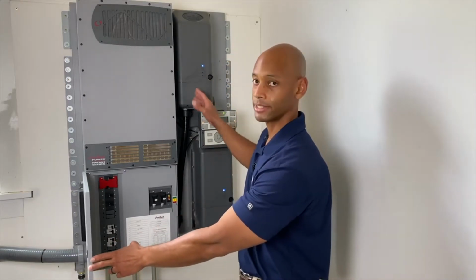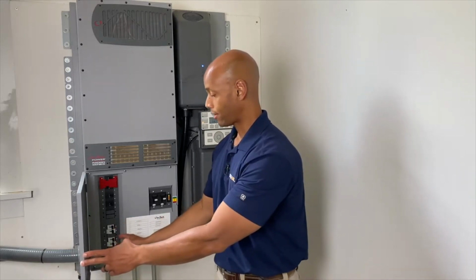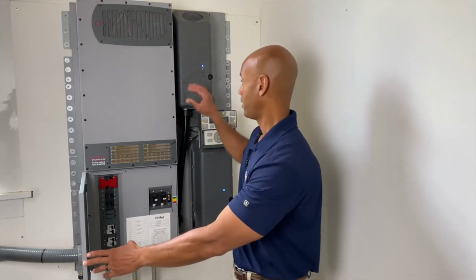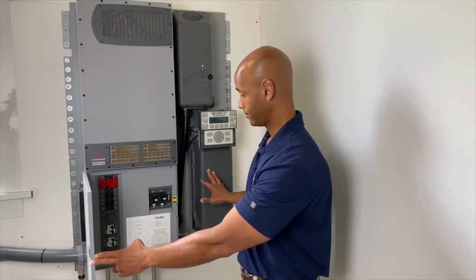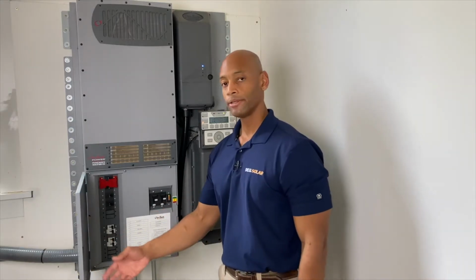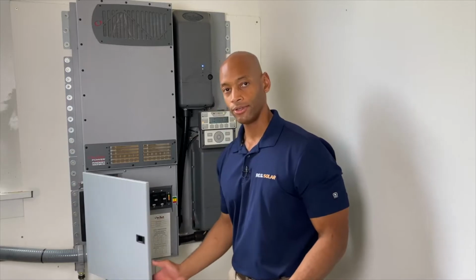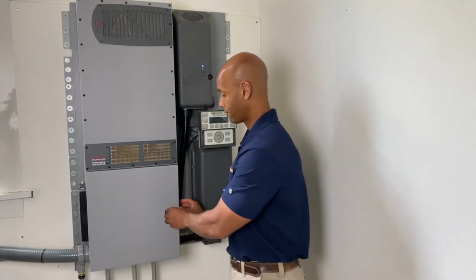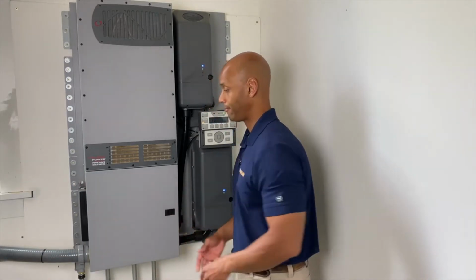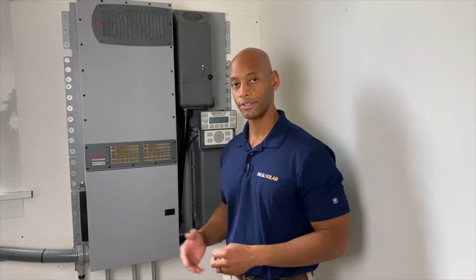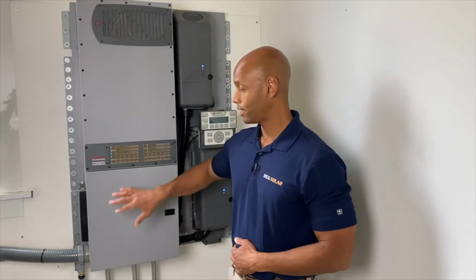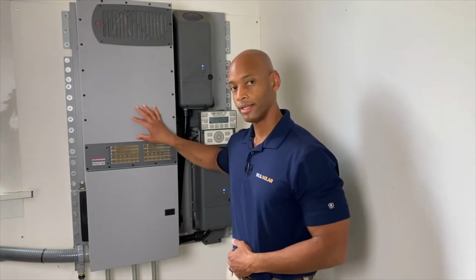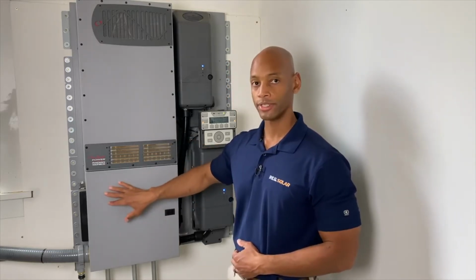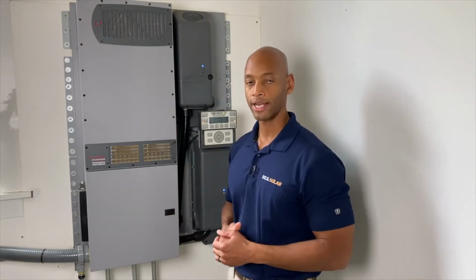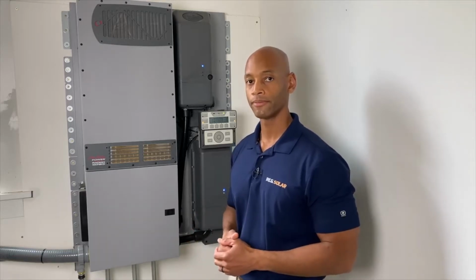If we had to service either one of these units, we just cut all the power sources off here, and then we can safely work on the equipment. So that's your switchgear. Not a whole lot you have to do here under normal operation. This can remain closed, but at least you know if you have to bypass the unit for service, you know how to do that. That way, if the inverter ever needs service, you can switch over to utility power and not be without power inside the home.